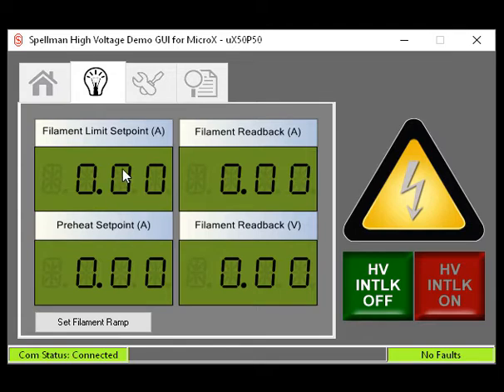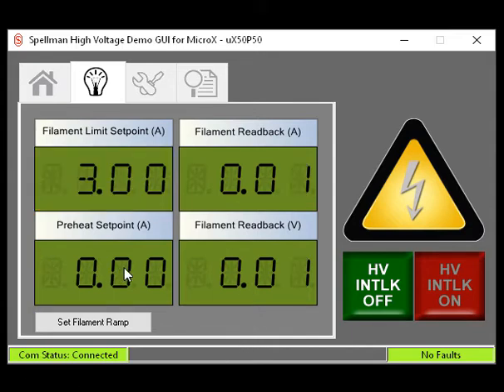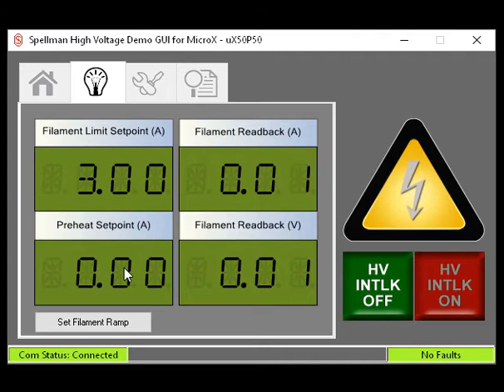Click the box and it will turn yellow. Type the value in and use Enter to exit. Next is the filament preheat set point. This is the amount of current that flows in the filament circuit when the X-ray generator is not in high voltage.